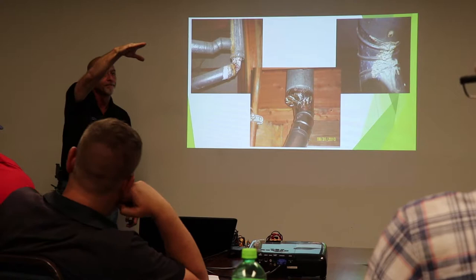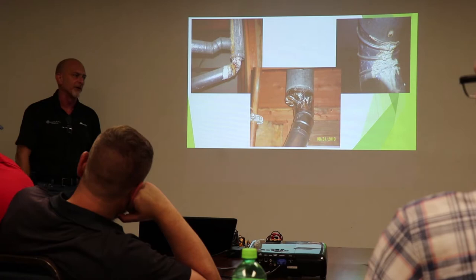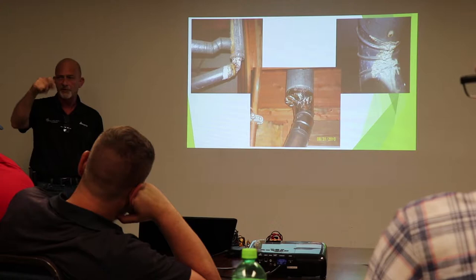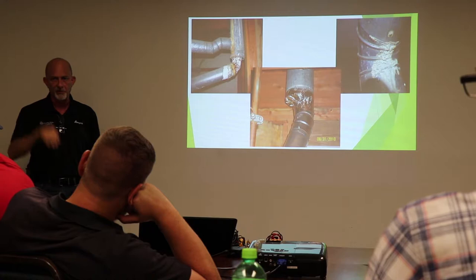What happens, you'll be having an intermittent problem. It'll work just fine while you're there. As soon as we get a long run cycle and that water fills up, it trips on the pressure switch, shuts off, eventually drains out, and fires back up. So pay attention to all your piping. Make sure we are pitched back to the furnace.